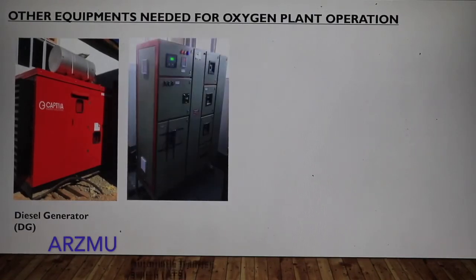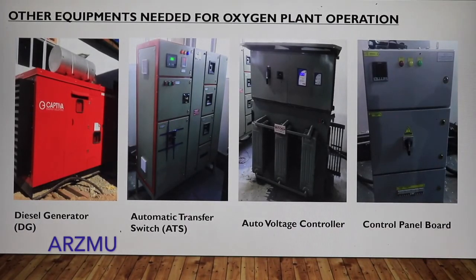The other equipment necessary for the operation of an oxygen plant are: a diesel generator (DG) for backup source of electricity, an automatic transfer switch (ATS) used to run the DG in case of power failure, an auto voltage controller for the oxygen plant, and a control panel board as a safety measure.